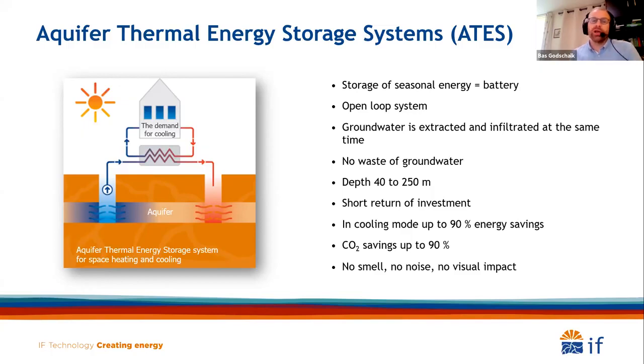You can imagine that when you abstract 7 degree water, you can use this temperature for direct cooling of your building. But when you abstract 17 degree water, it's too low a temperature to heat directly, so you use a heat pump to increase the temperature level to about 40 to 45 degrees, and then you can heat your building.